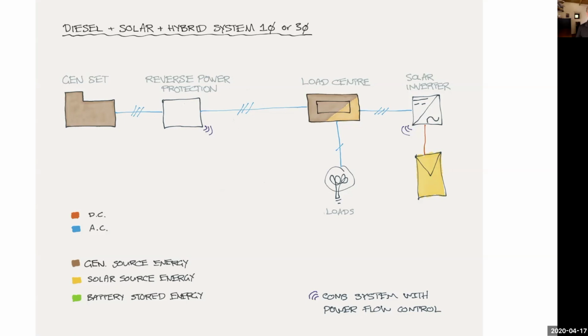But generators don't like reverse power. Unfortunately, you can't feed power into a generator and make diesel. It's a one-way device. So you need some form of reverse power protection in a design like this that may be built into the generating set. Many quality generating sets have reverse power protection as standard, but it may be a standalone product that ensures that you don't backfeed a generator and cause it to stall or even fail. So that is a little bit of an unusual one, but more likely a commercial off-grid site.